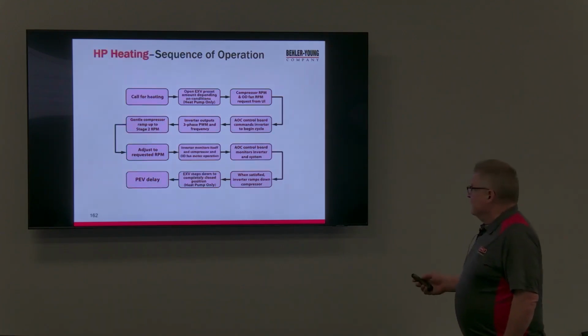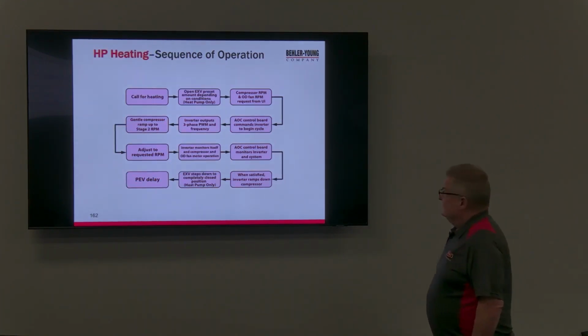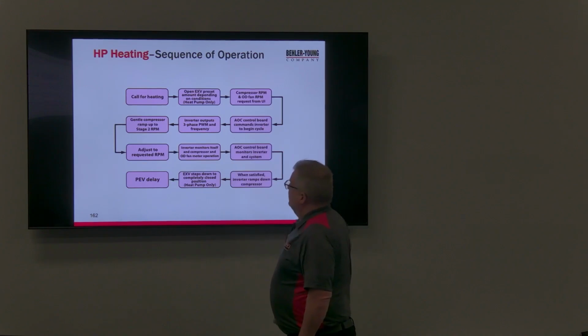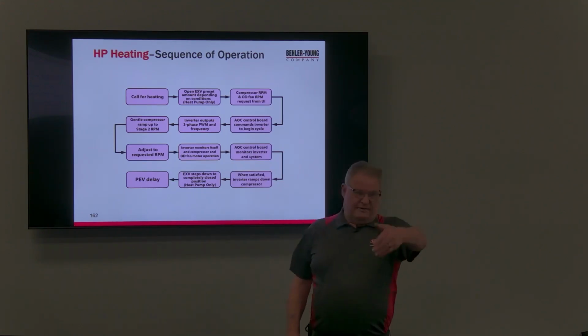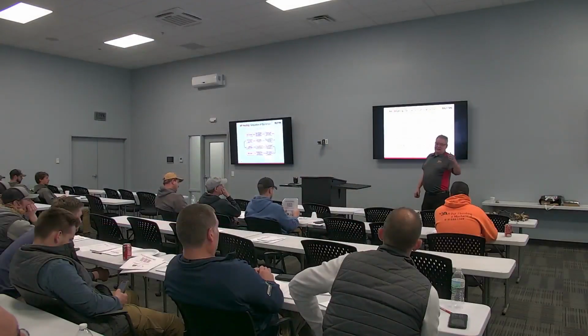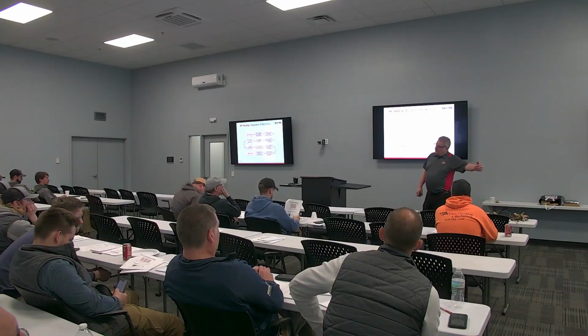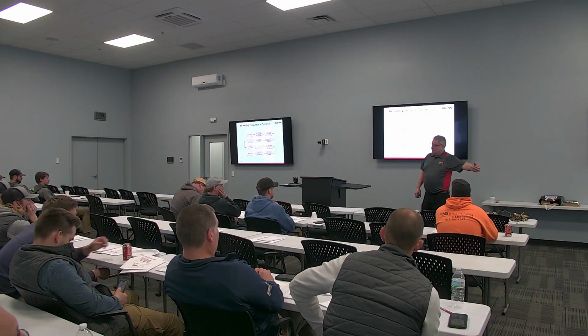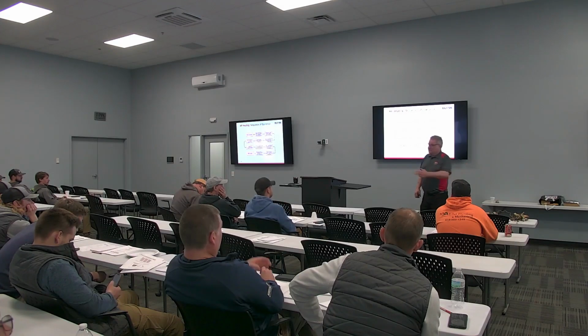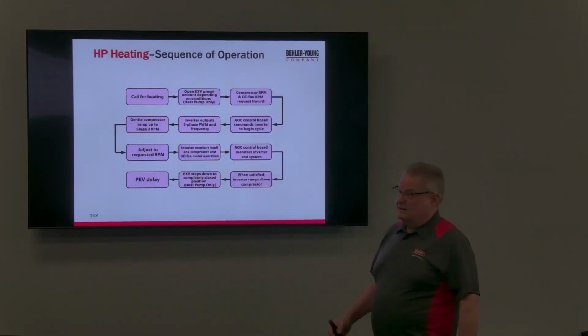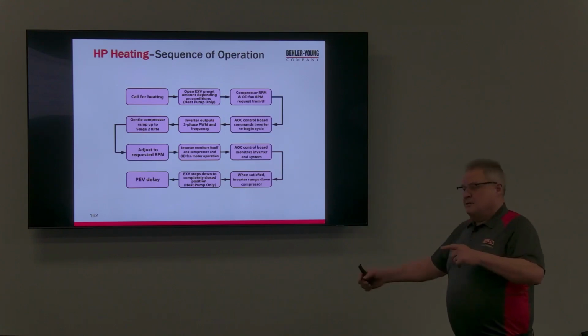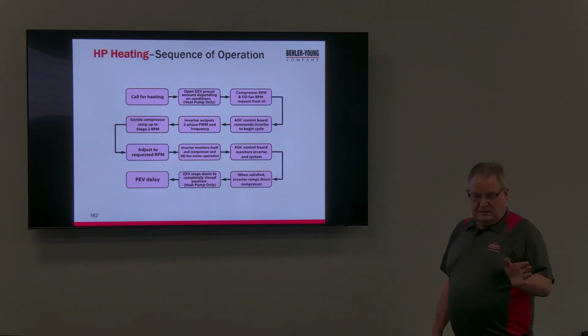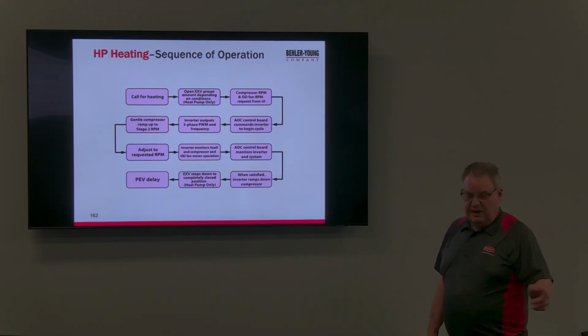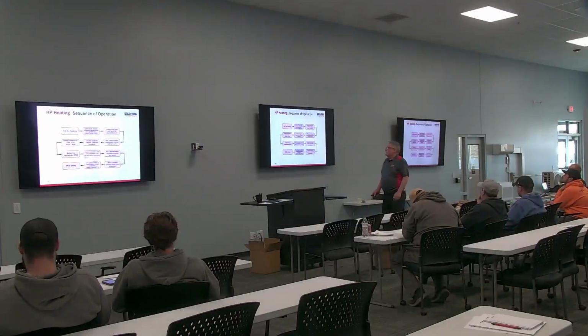All right. On the call for heat, open the EXV a preset amount, so it'll probably go to 50%. The EXV in the condenser unit, because now remember the flow, the liquid line is now not the liquid line, it's the saturated line. Or I mean the other way around, it's going to come to the condenser unit through the liquid line. It's going to meter through the expansion valve, go through the outdoor coil, which is now the evaporator, and then go back to the compressor.